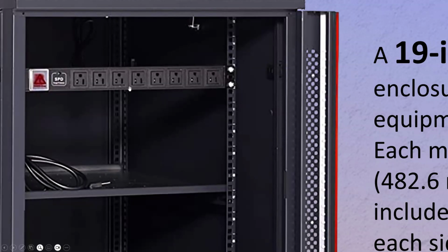PDU stands for Power Distribution Unit, which is basically a glorified name for a power bar, and it has glorified functionality too. There are different PDUs - you can buy them with a bunch of outlets on the front, or hydro outlets at the back and a couple at the front. There will be certain lightning or surge protection included in those. Some of them are sequential power bars or sequential PDUs, which means that if you turn that thing on and a whole bunch of equipment is being powered, some having heavy current draw initially, you'd just blow the fuse.